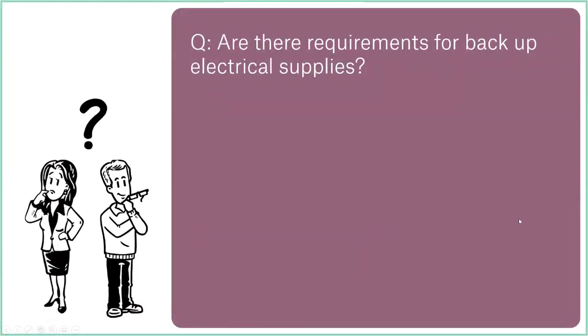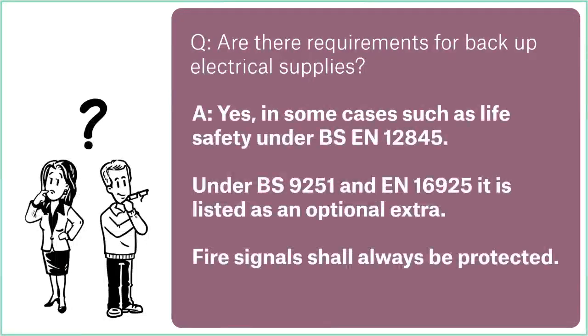Requirements for backup electrical supplies. So yeah, in some cases, yes, you would need backup electrical supplies. Under the domestic and residential standards, it is there as an option, and where there's an option, generally people don't do it, of course. Fire signals always should be protected. So fire signals should not be relying on mains electricity to get those signals through. Obviously, they're very important. And it's not such a big deal to have a battery on your panel. So, I can't think of any panel that won't have a battery backup on it for that very purpose. The main panels I'm talking about. So they have a battery on there so that when the mains power goes down, they've still got that communication.